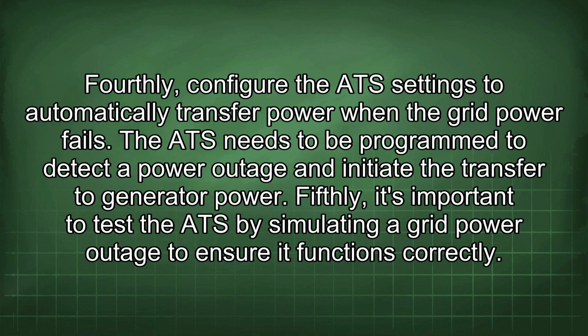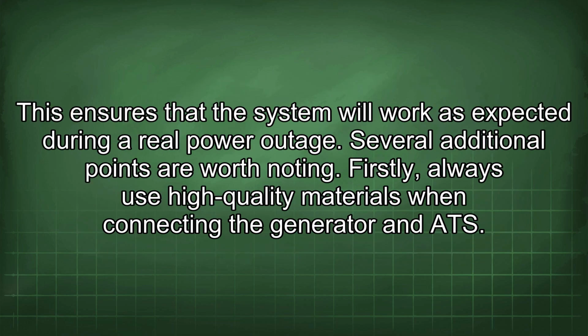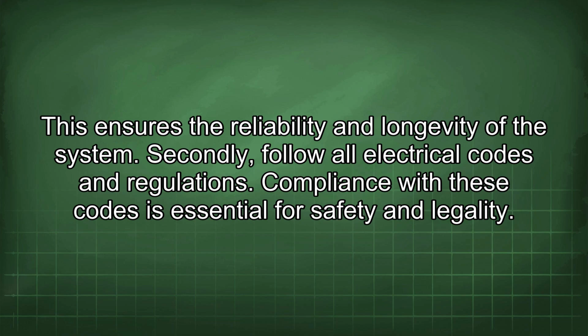Fifthly, it's important to test the ATS by simulating a grid power outage to ensure it functions correctly. This ensures that the system will work as expected during a real power outage. Several additional points are worth noting. Firstly, always use high-quality materials when connecting the generator and ATS. This ensures the reliability and longevity of the system.